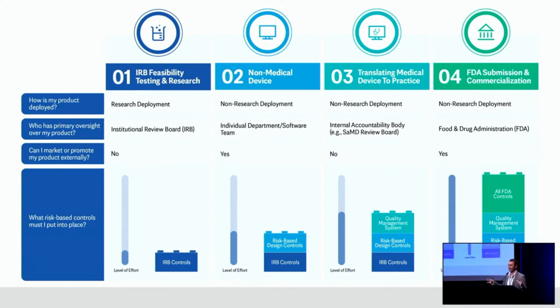But I think I like to think about it differently in terms of if you've gone through the IRB controls to do your research, you've already started your deployment controls. When you get to stage two, if you have a non-medical device, which by nature is a little bit lower risk, you can add design controls, risk-based design controls to that research and maybe go into deployment mode. But you're still using the artifacts that you've generated in research to execute on your design controls.